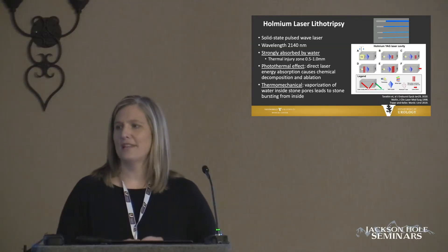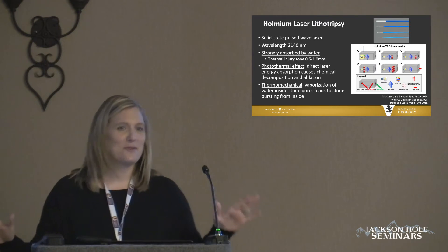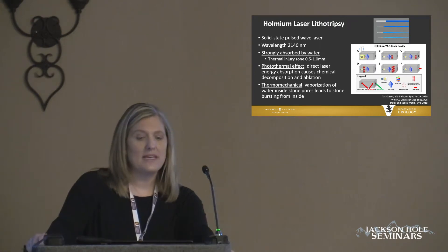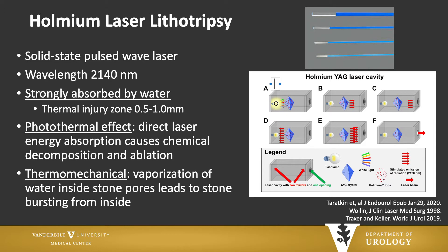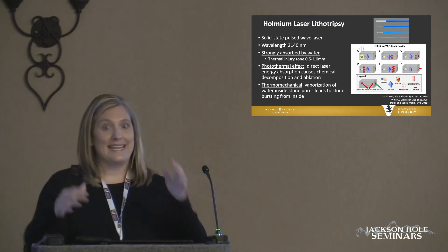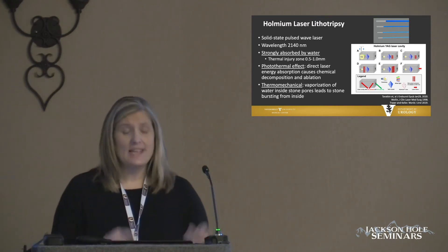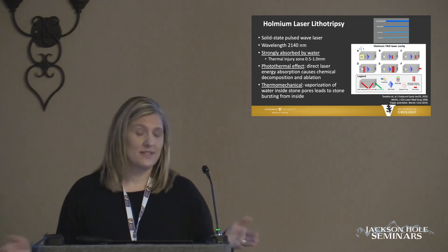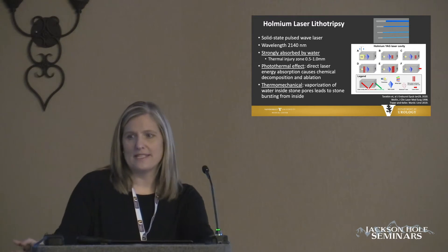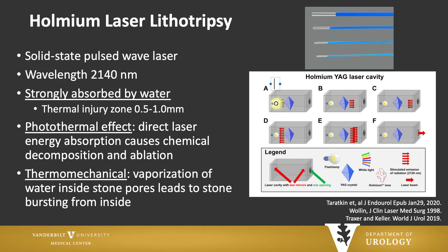Who in the audience knows how your laser works? There's no quiz, I promise. The Holmium laser has been identified by the EAU guidelines as the preferred laser for flexible ureteroscopy. It is a solid-state pulsed wave laser. High voltage energy from the wall is pumped into a flash lamp, absorbed by a crystal containing Holmium ions, excited, and then emitted as radiation. Two reflective mirrors amplify that energy, which exits the laser at a wavelength of 2140 nanometers — strongly absorbed by water — making it both safe and effective.